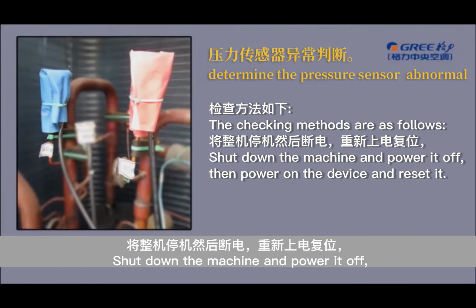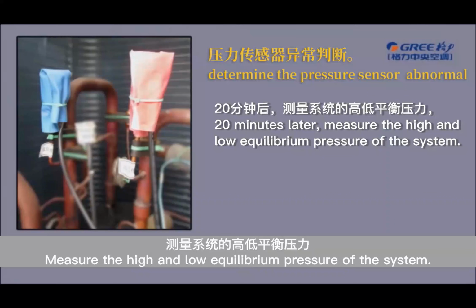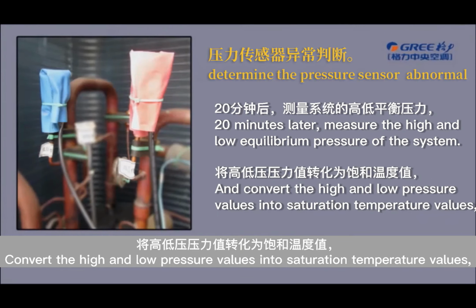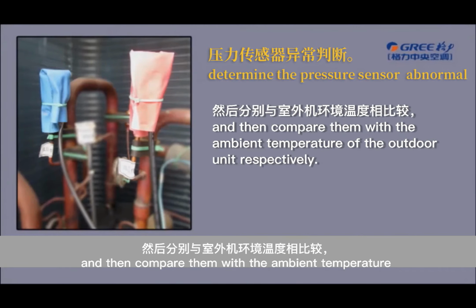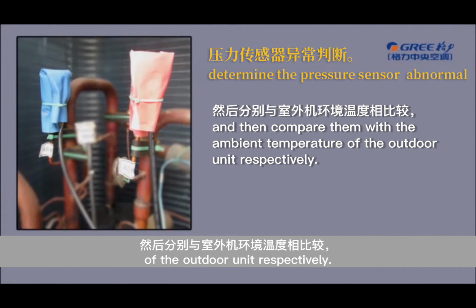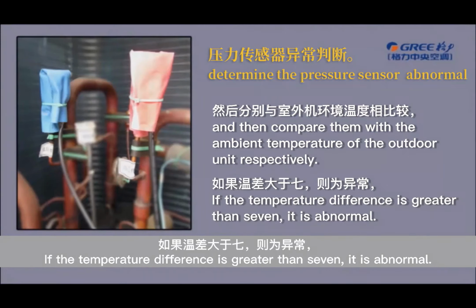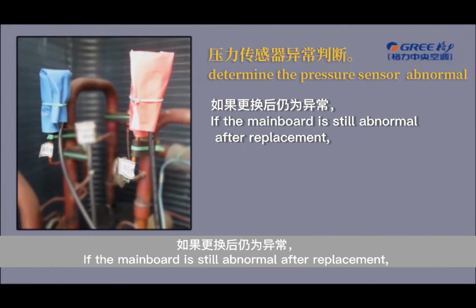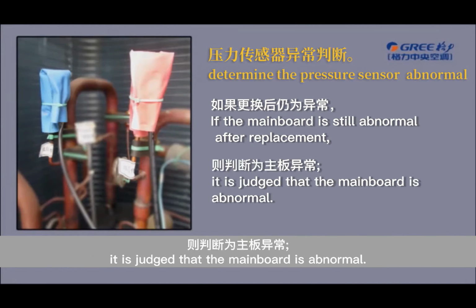Shut down the machine and power it off, then power on the device and reset it. 20 minutes later, measure the high and low equilibrium pressure of the system. Convert the high and the low pressure values into saturation temperature values, and then compare them with the ambient temperature of the outdoor unit, respectively. If the temperature difference is greater than 7, it is abnormal. If the main board is still abnormal after replacement, it is judged that the main board is abnormal.